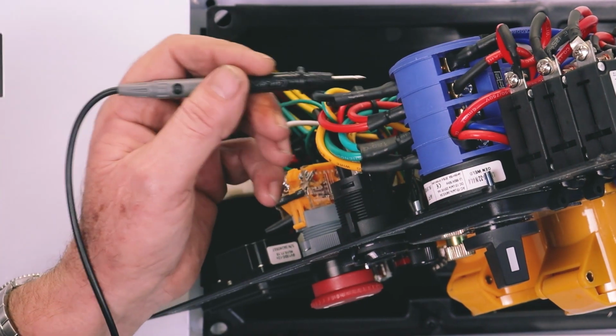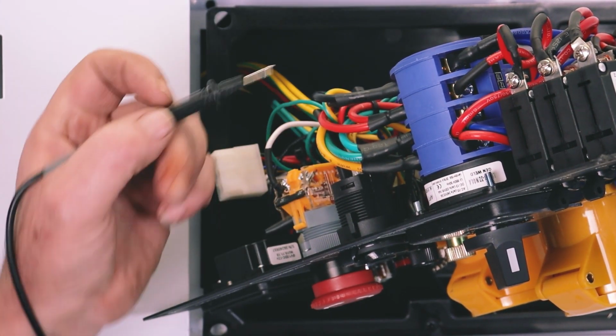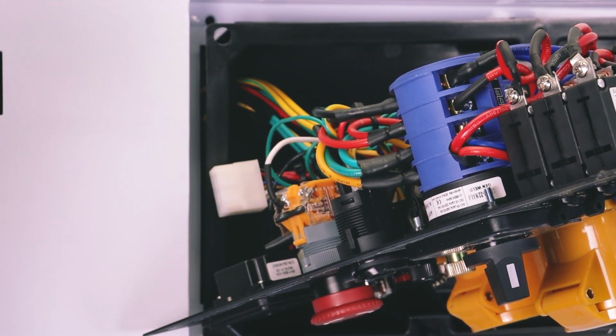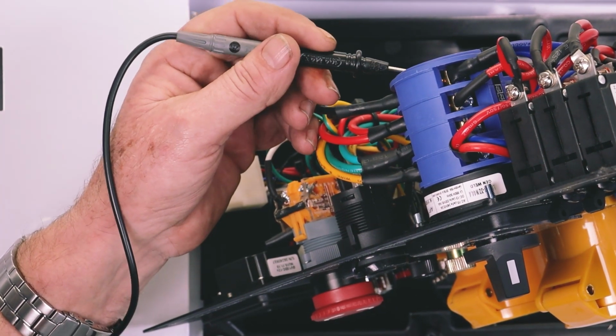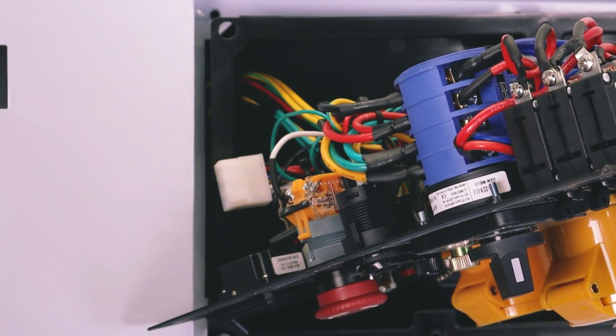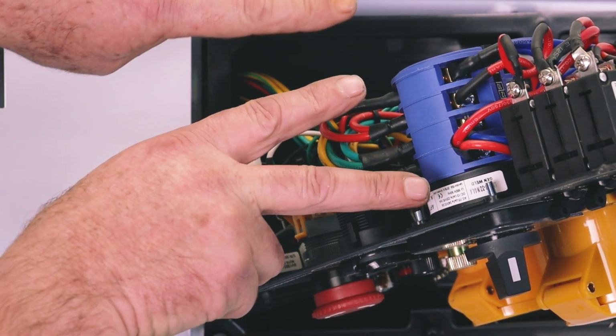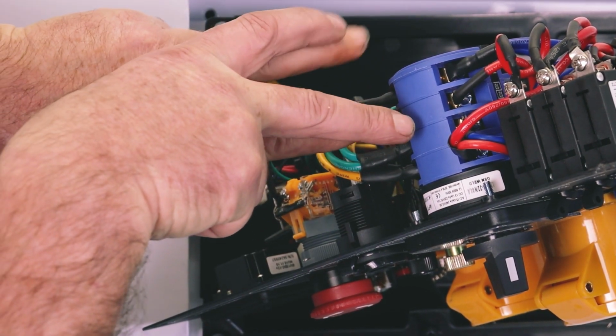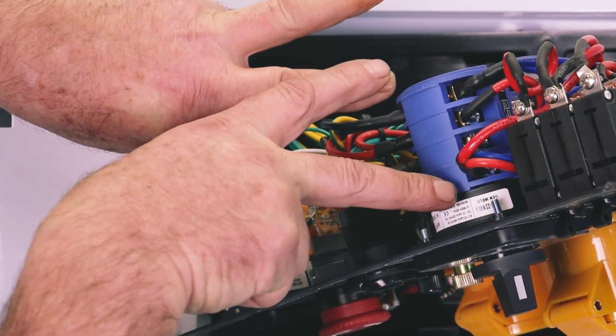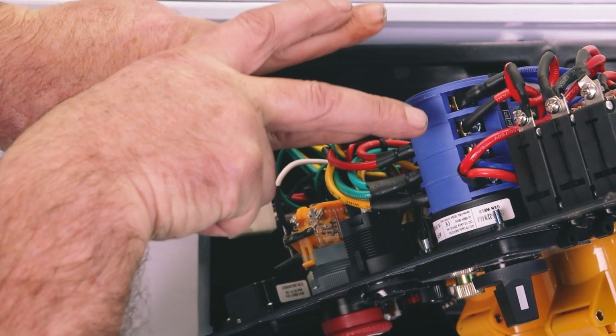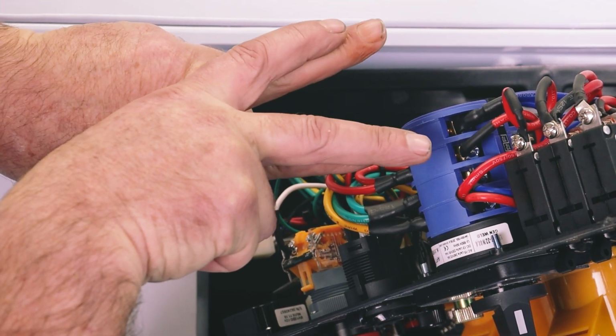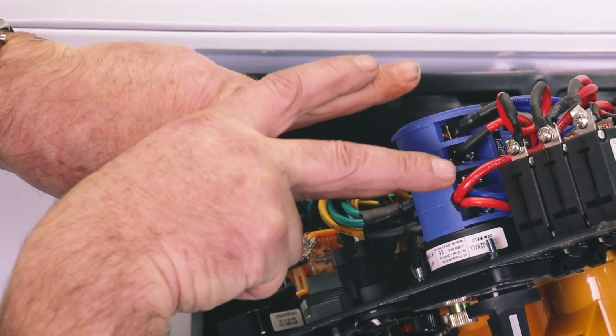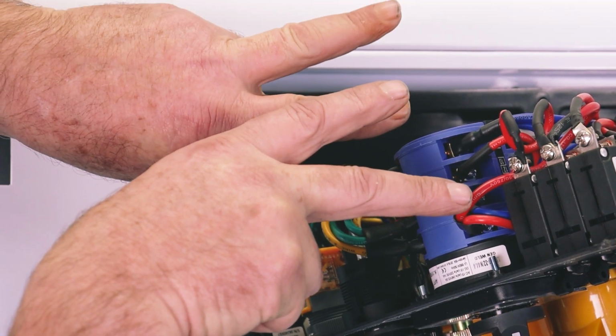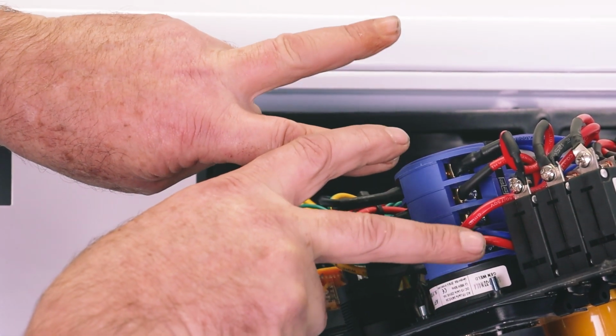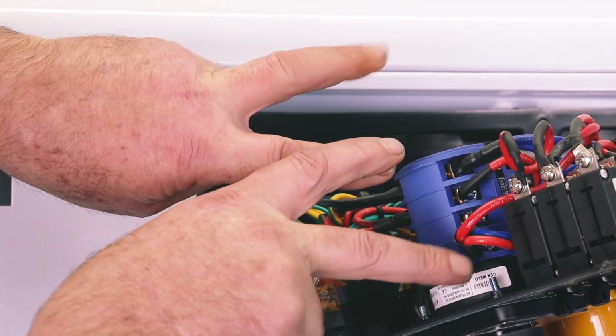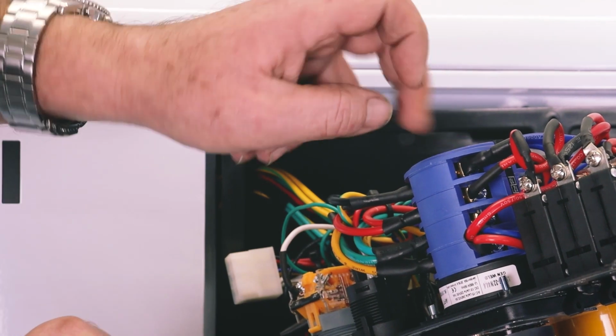The alternator puts out 2 115 voltages - think of it as 2 separate alternators in sequence with each other. When we're using the 115 outlet from the machine, the changeover switch takes the 2 115s and joins them so we've got 115, with 2 windings joined together giving a positive and a negative. When we're in 230 mode, the changeover switch changes it so the positive of one 115 and the negative of the other join in the middle, giving us negative, positive, 230 across the outside. That's the purpose of the changeover switch.